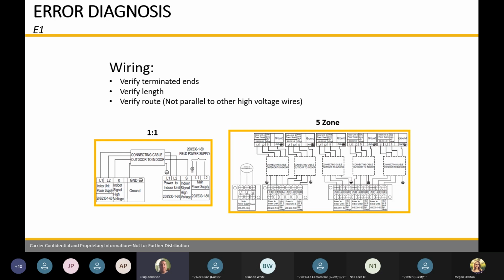So if you're getting a call with weird stuff like that going on, always go back to the wiring to make sure that it adds up to the indoor and outdoor unit. We get that probably about 6 times a year. They mixed up the wiring. It's doing erratic things.